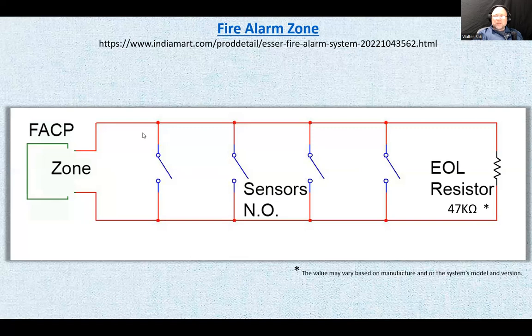All right, now, as opposed to security alarm, where the system is a closed loop and when the system opens, it triggers alarm, here it's the opposite. All the sensors are normally open. When they trigger, they close. So what happens here? We have different conditions. If the line is broken, the zone is not going to see the end of line resistor, and it's going to go into a trouble condition. Trouble condition is just a bunch of annoying beeps from the panel, so somebody's going to get up and check what's going on, and it's going to say, trouble, call so-and-so for service. Then they're going to call for service, and service people are going to come and find out what's going on. Usually there's some kind of a line broken or ground broken or something like that. Now, that's the trouble condition. It's not a fire alarm condition.